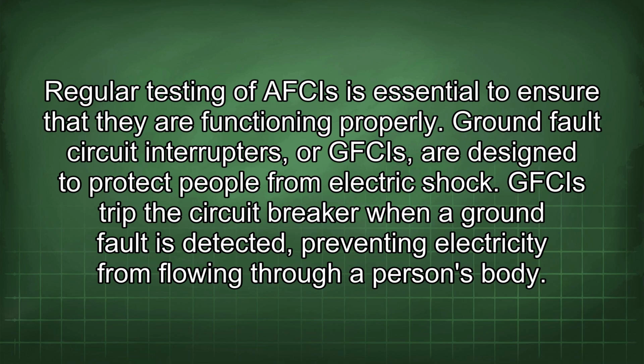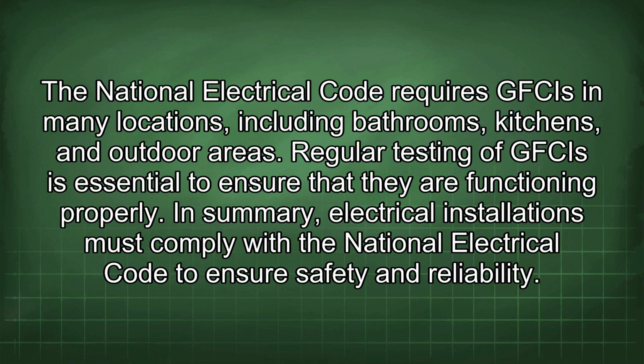Ground fault circuit interrupters, or GFCIs, are designed to protect people from electric shock. GFCIs trip the circuit breaker when a ground fault is detected, preventing electricity from flowing through a person's body. The National Electrical Code requires GFCIs in many locations, including bathrooms, kitchens, and outdoor areas. Regular testing of GFCIs is essential to ensure that they are functioning properly.